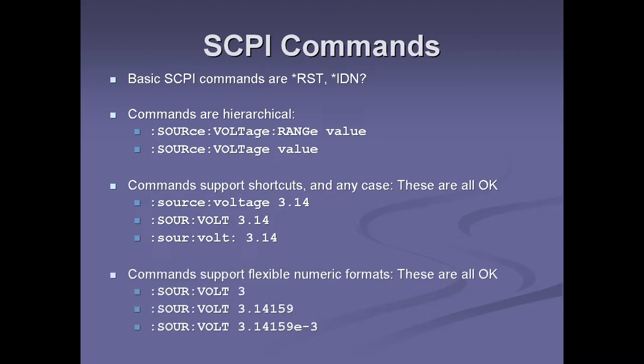Commands also support flexible numeric formats. These are all okay. So I can say SOUR:VOLT 3 to set the voltage to 3, or I can say SOUR:VOLT 3.14159, or I can say SOUR:VOLT pi millivolts if that's what I want.